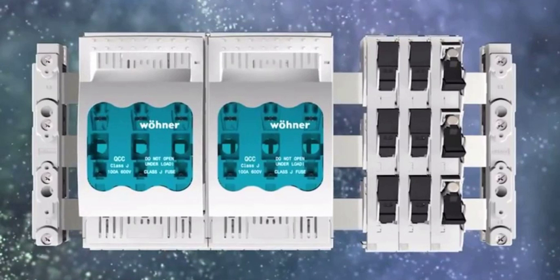Topic: disadvantages. Commercially not viable if the number of switchgears is low. Specialists needed for construction of the busbar system from a wiring diagram. Lack of adapters for mounting different electrical devices on the busbar. Special type of busbars needed to construct busbar system which can carry current of more than 800 amps.